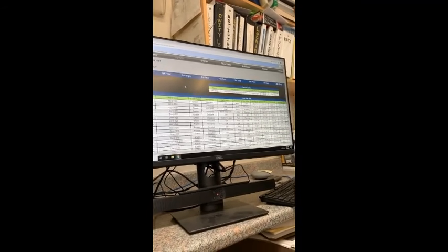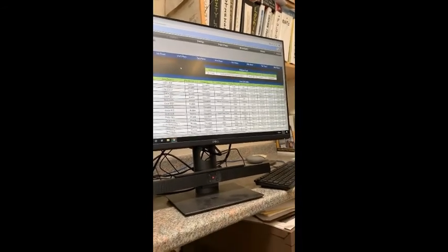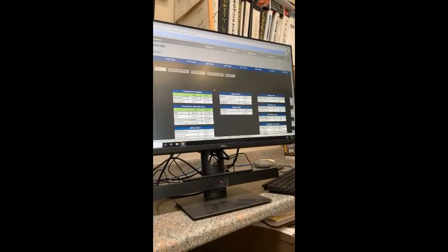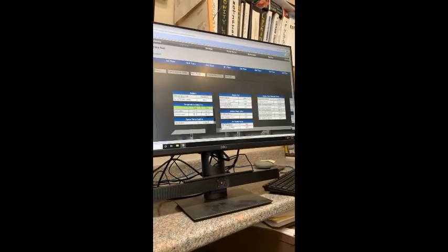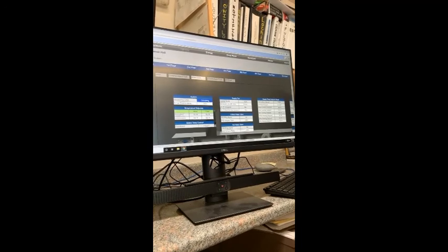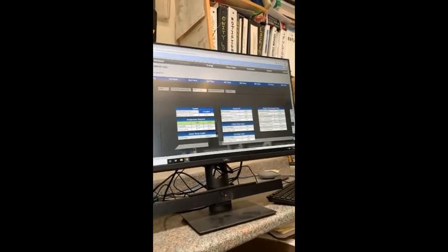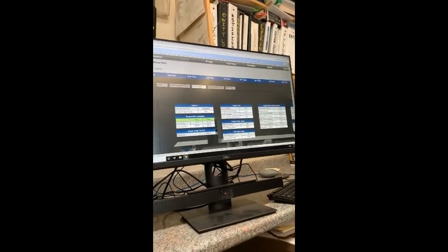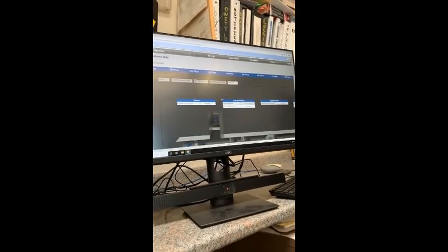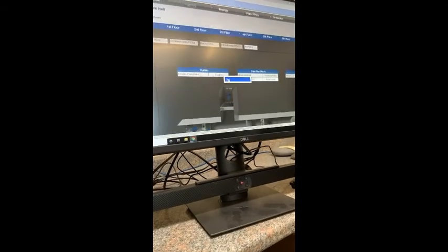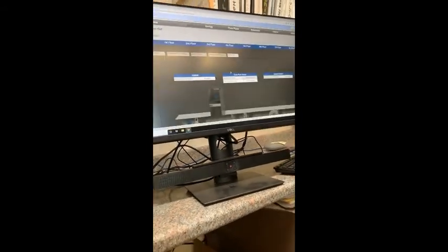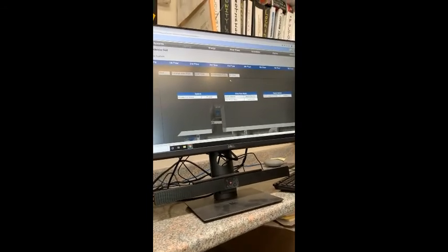So if these buildings are vacant, can you go in there and turn them all off? Yes. That is in the global options. Say you could go to the dorm rooms, you could set them all to not being occupied. For all fan coils, you can actually disable the system. Shut off the apartments also, and every fan coil would be disabled.